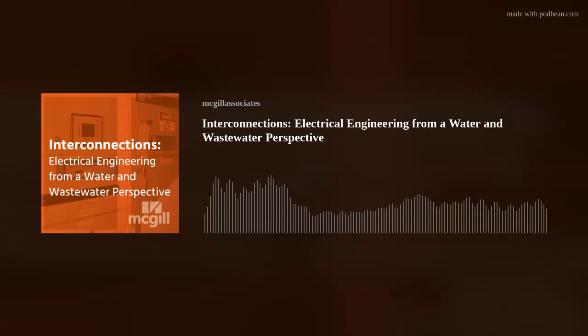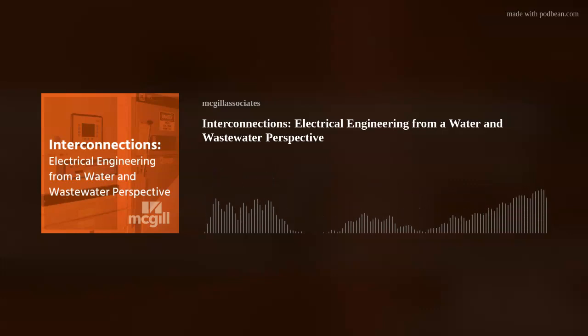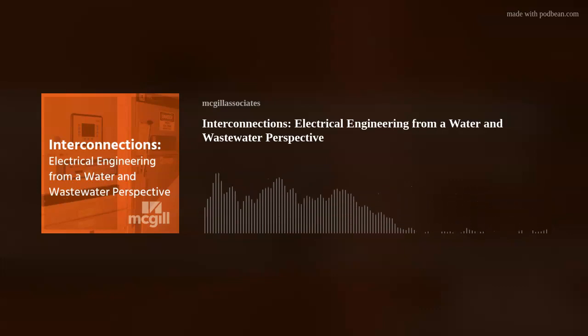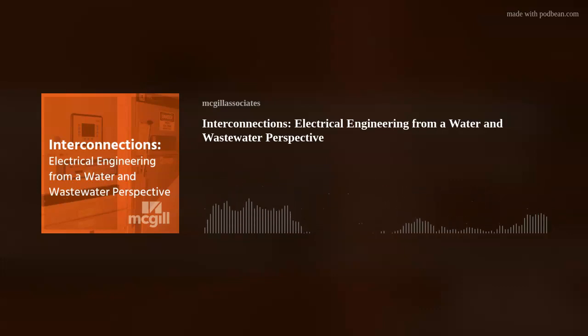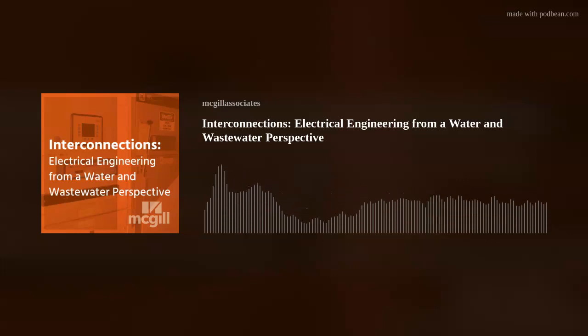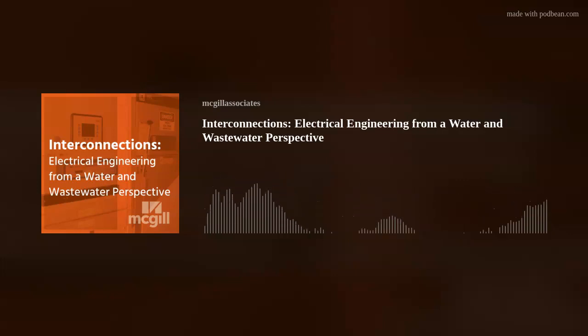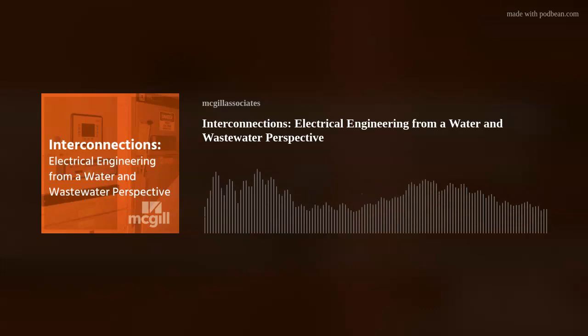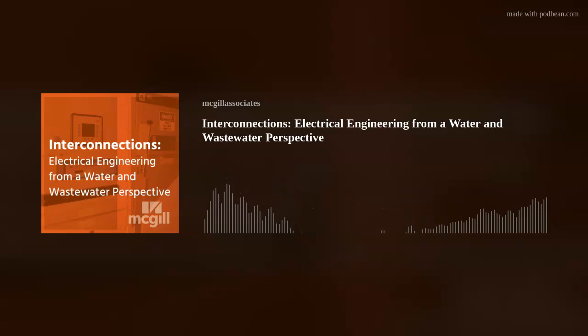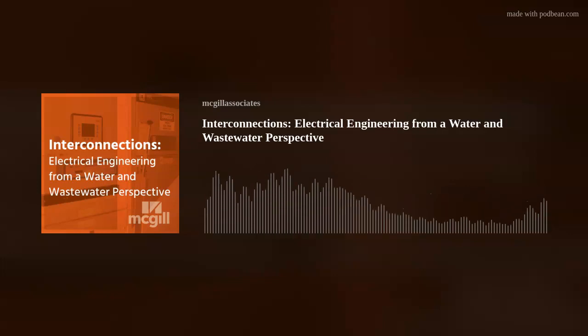With a SCADA system, you're able to automate a process through various logic and algorithms. A process that gets handled remotely with a hands-off approach is a sewer lift station. These stations are typically remote and can be numerous in the system, depending on the terrain, valleys and things, requiring pumping wastewater up and then gravity feeding down to the next one. These typically operate off local controls, which monitor the level in the wet well to turn the pumps on or off based on that level. You've got various input devices, float switches, bubblers, ultrasonics, or pressure transducers used to monitor the water level and turn the pumps on and off.